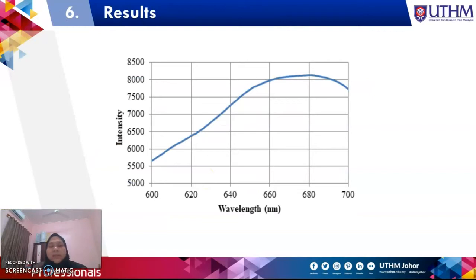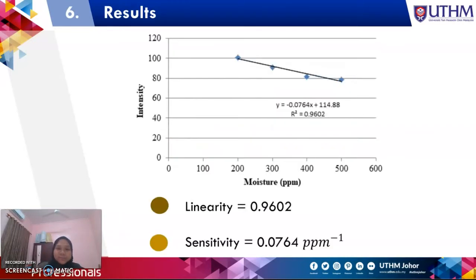For the result, this is the graph of the output spectrum for the reference oil, where we can see the peak of the spectrum is at 680. So we use this wavelength as the reference wavelength to analyze the data for the four different moisture contents in the transformer oil. As you can see here, this is the graph for the four different moisture contents in the transformer oil. Using this graph, we get the linearity and the sensitivity of the POF moisture sensor.